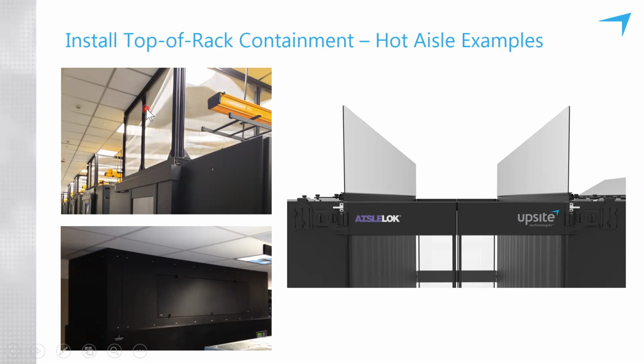So the hot air is going to be filling the hot aisle, and hot air rises. So it's going to rise up and be drawn back to the intake of the perimeter air conditioning units in that room. And the key is that they are also ducted directly to the overhead plenum, like you see in the photo on the bottom right. That's black ductwork sitting on top of one of the new Vertiv AC units that's a similar color. You can see there's a hinged door so you can get in and change filters, but that's a key component to making all of this work. Everything's ducted to an overhead ceiling return.